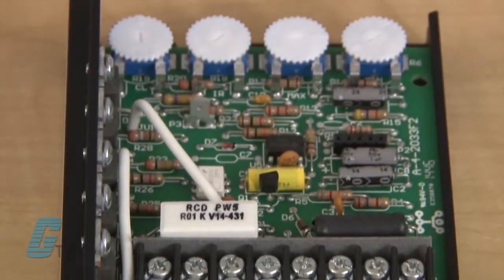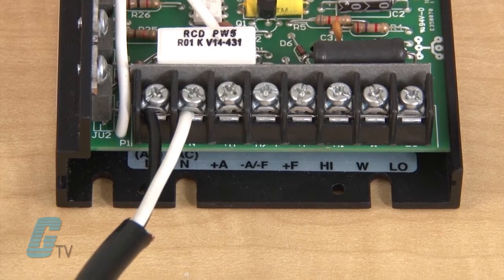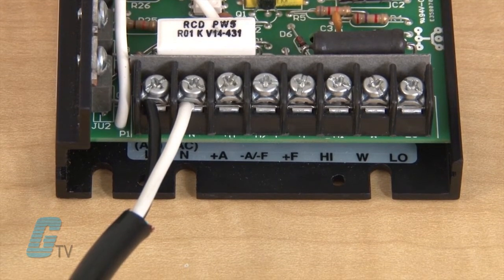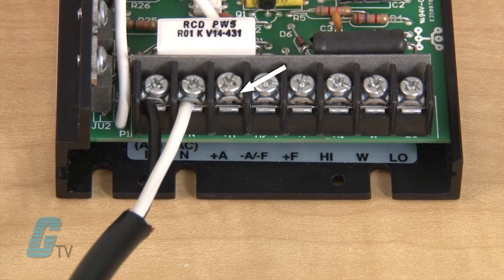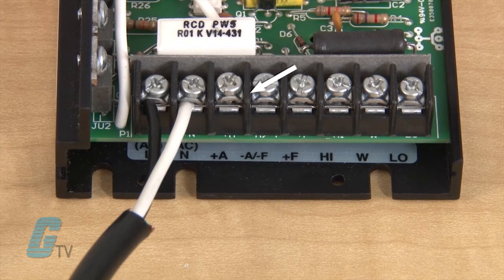Next I will need to make my motor connections. A shunt wound motor will need to have the armature and field connected. The third terminal here is the positive connection of the armature and will connect to the motor's armature. The fourth connection is the negative side of the armature and field.